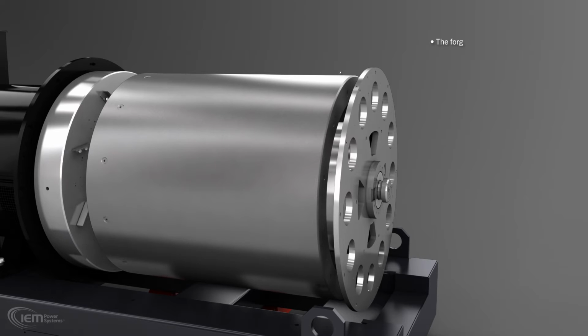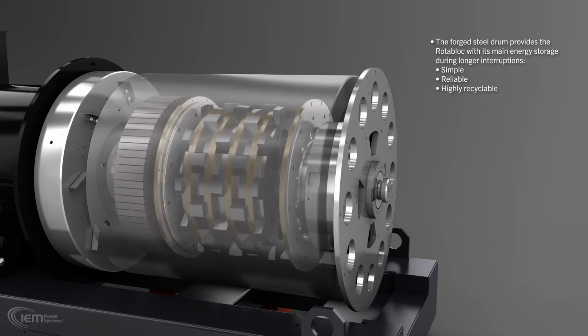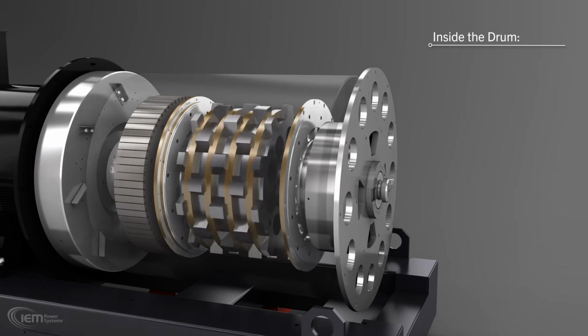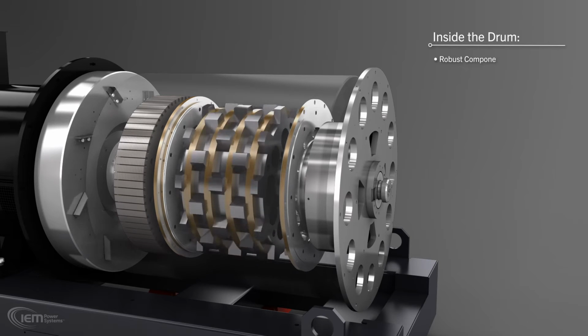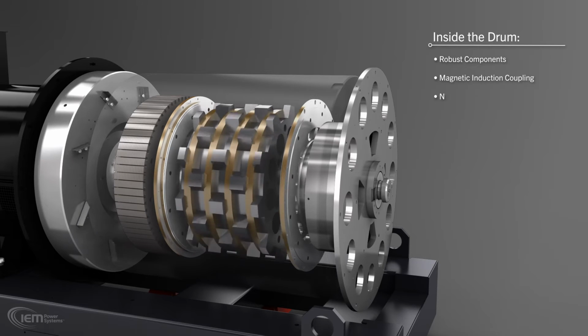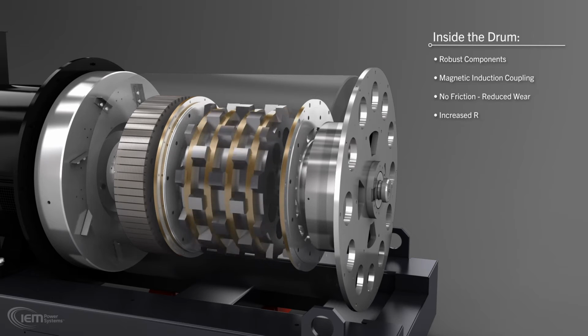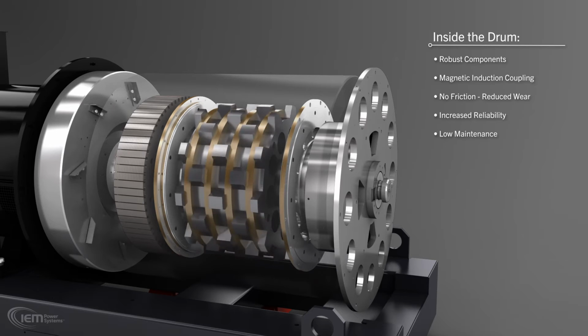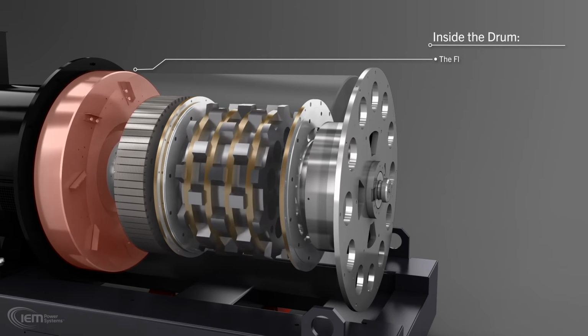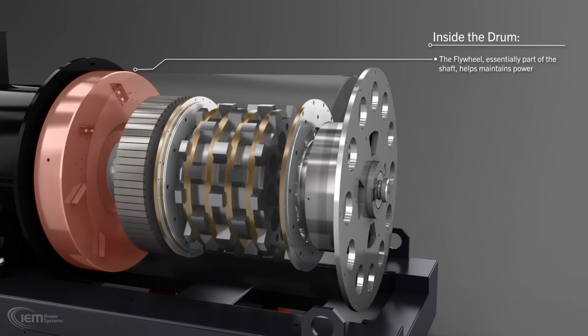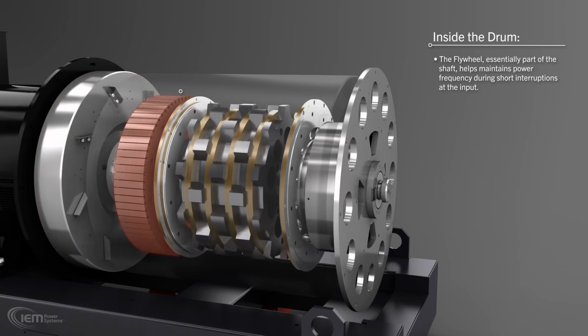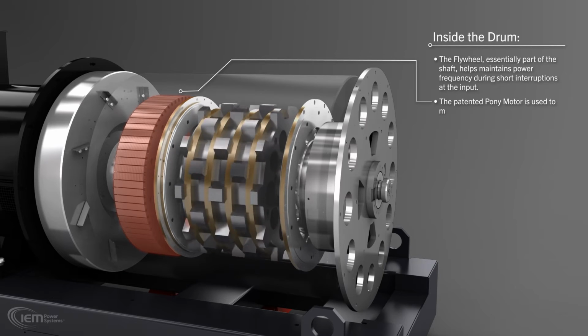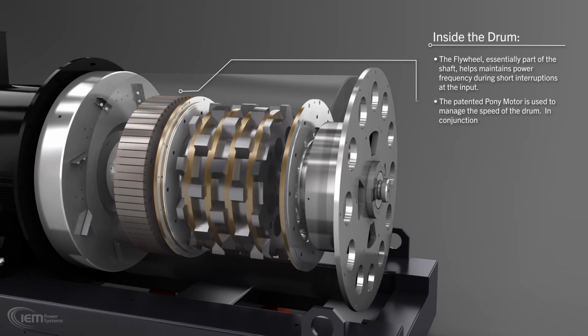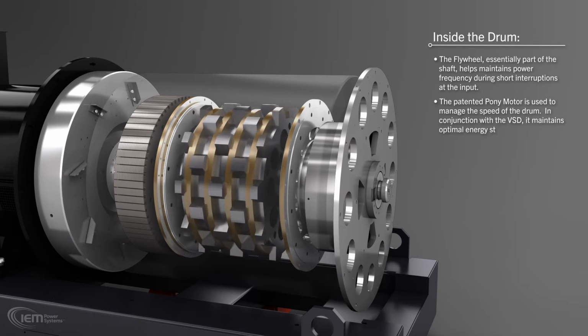The forged steel drum provides the Rotoblock with its main energy storage for use during longer interruptions. It is simple, reliable, and highly recyclable. Inside the drum, robust components allow the energy stored to be transferred to the alternator shaft when required. The Rotoblock uses a magnetic rather than mechanical coupling, reducing wear, increasing reliability, and minimizing maintenance. The flywheel, essentially part of the shaft, helps maintain power frequency during short interruptions at the input. The patented pony motor is used to manage the speed of the drum. In conjunction with the VSD, it maintains optimal energy storage for the system.